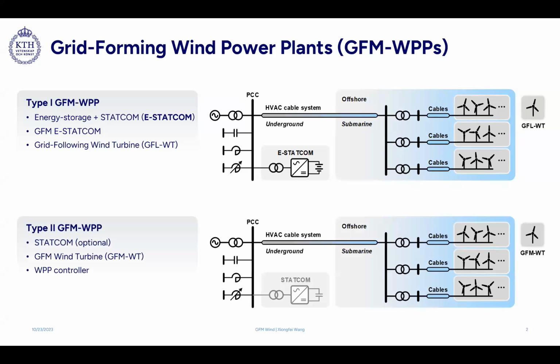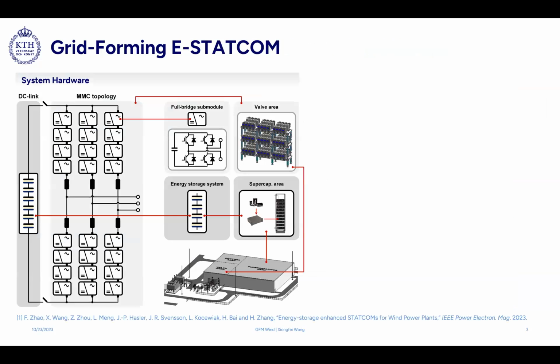The second type of wind power plant is based on the grid forming wind turbine. In this case, we can have a STATCOM or not have a STATCOM. It's really dependent on the length of the AC transmission cable. Those 2 types of grid forming wind power plant are based on our industry projects with the energy developers and also OEMs. So let's first look at the grid forming eSTATCOM.